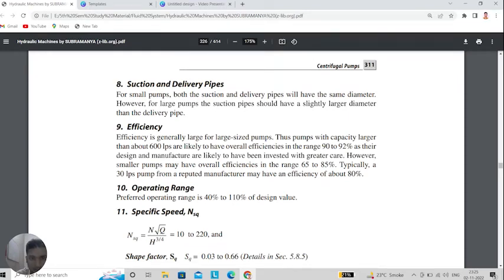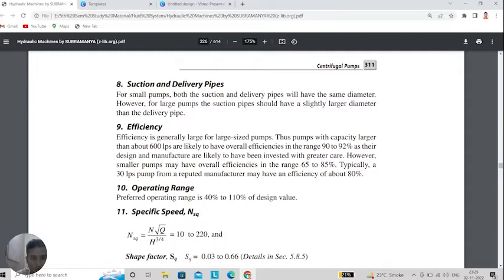Suction and delivery pipes: for small pumps both pipes have the same diameter, however for large pumps the suction pipe has slightly larger diameter than the delivery pipe. Overall efficiency must be in the range of 90 to 92 percent for a better pump, and for smaller pumps the range is 65 to 85 percent. Overall operating range is from 40 to 110 percent. Specific speed Ns equals N·√Q / H^(3/4), which ranges from 10 to 220.